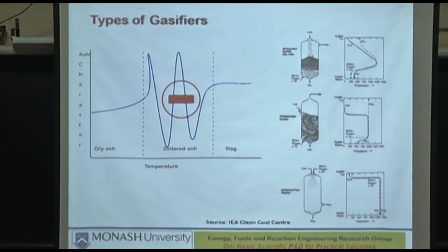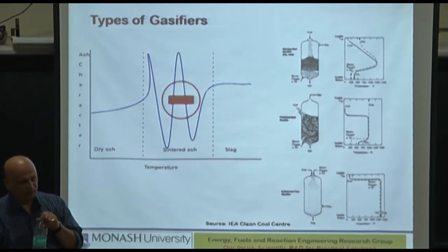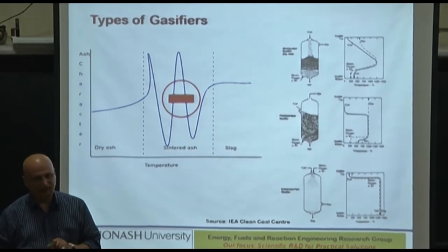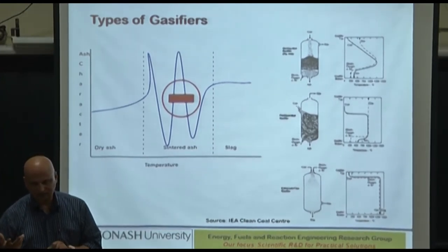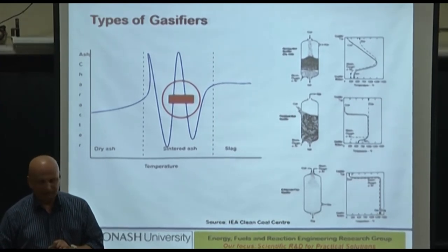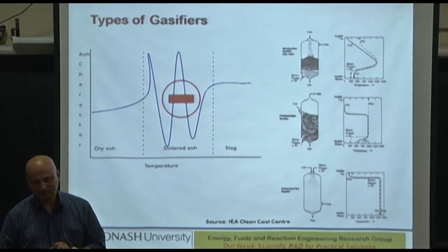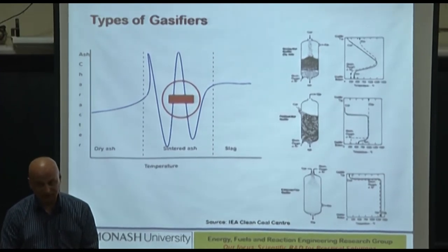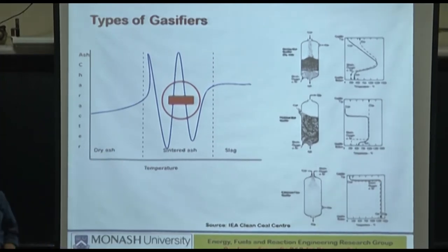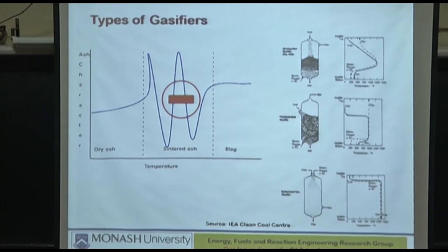Very much so. Because you see, if you don't take the spent material out of the gasifier at the bottom, it will simply build up, and it is going to affect the heat transfer considerably. Ash is a compact thing. Char is a porous thing. Char requires unimpeded access to oxygen and heat. It will not get it if ash is there. So you have to take the materials out on a regular basis. And taking out the material on a regular basis is so much easier in an engineering sense, nothing to do with chemistry, if it is in this form, because its character is predictable. Right?